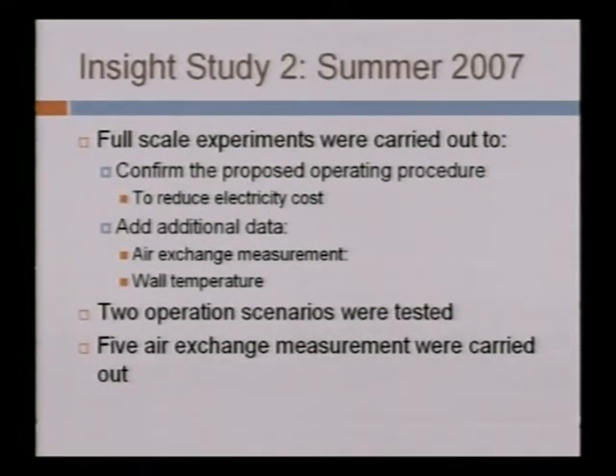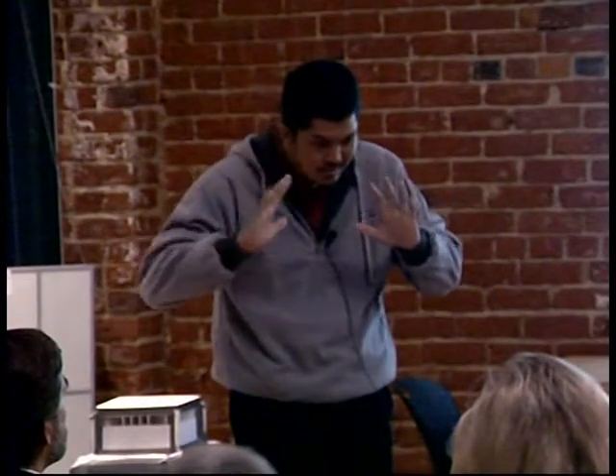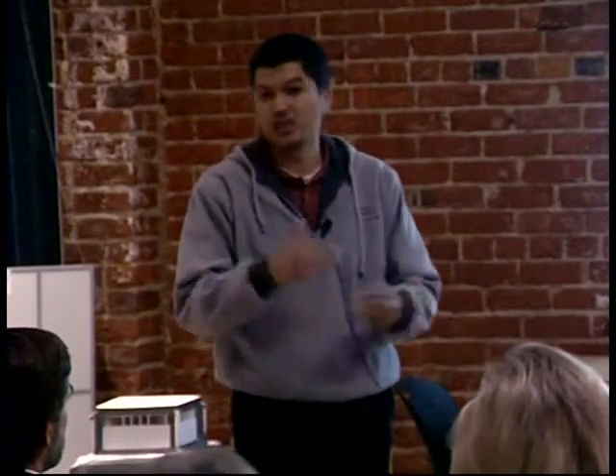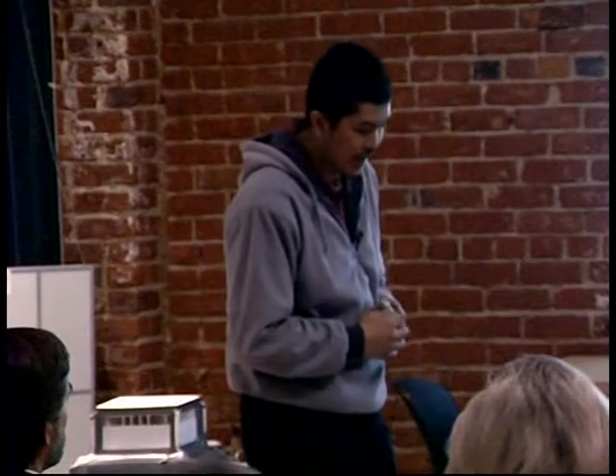So we decided we need to do another study to get it right. The second thing is that when we talk about night flush, how much air do we need — how much air from outside really blows into the space during the night? We didn't study that in the first round, but it's a very important parameter. 3 air changes per hour for the whole night compared to 10 air changes per hour will make a big difference, and we want to study that.